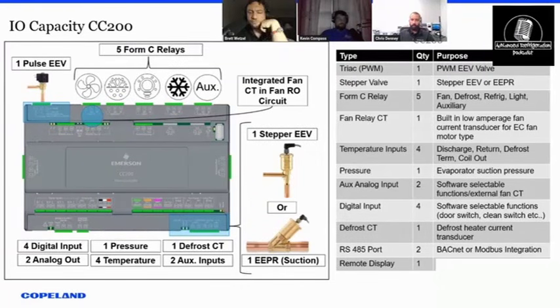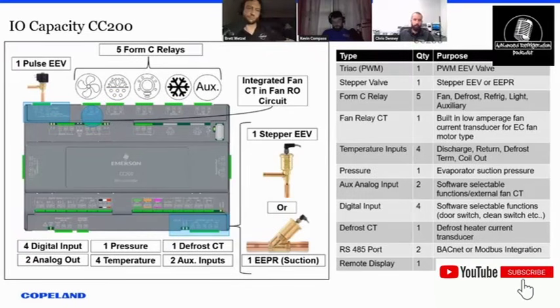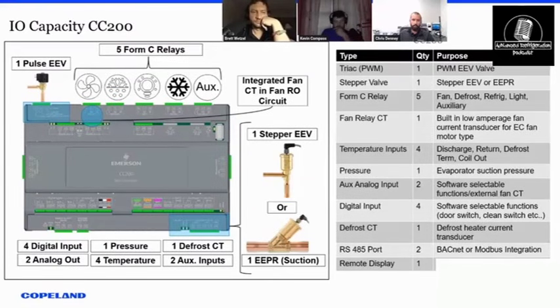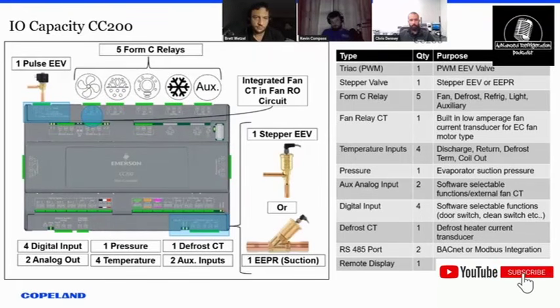Moving along the bottom here, we got some digital inputs that are all flexible, where you just define a purpose for those, so like door switch. We've got some clean switch input. We've got a leak detection input for customers that use leak detection systems that want to do a shutdown. We got our pressure inputs down here for the suction pressure transducer. And as Brett pointed out earlier, it's color coded to our Emerson Copeland pressure transducer harness. And then your standard temp inputs, green for the discharge, orange for defrost term, and purple for return air.